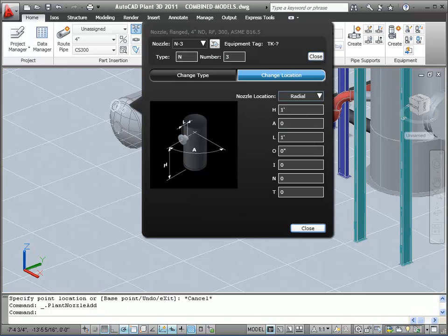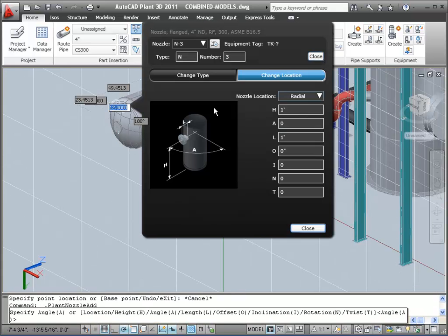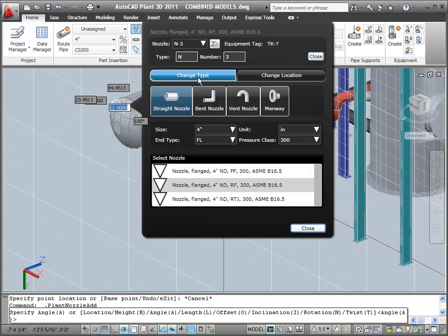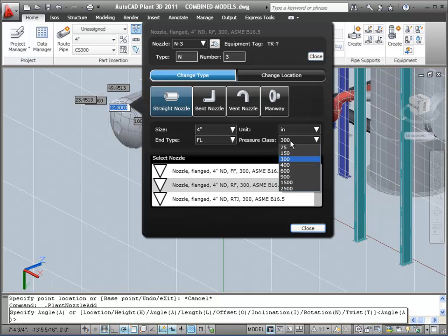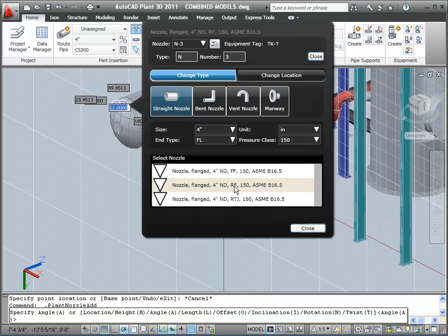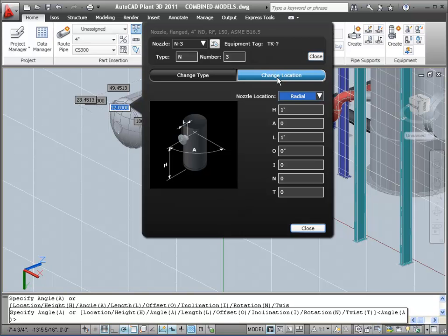We want to add a 4-inch, 150-pound, raised-faced nozzle and set its location on the vessel. In the dialog box, I'll click Change Type and make sure I'm filtering on a flanged end type, 4-inch nominal diameter, and 150 pounds. Then I'll pick the raised-face, 150-pound nozzle from the list.